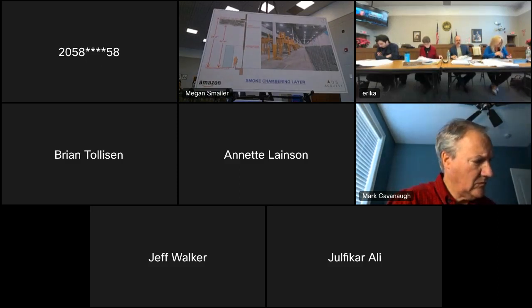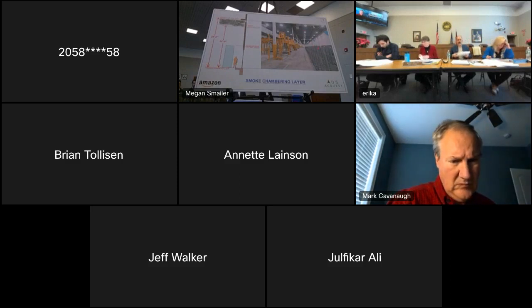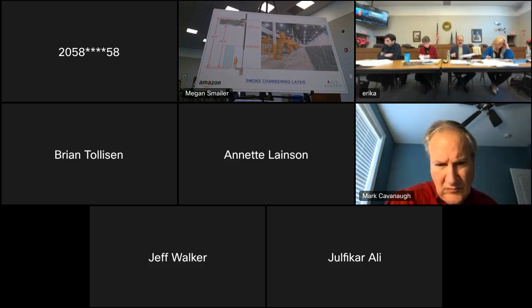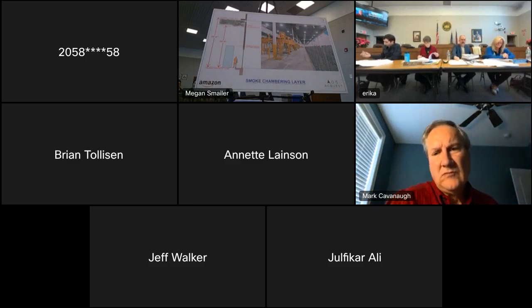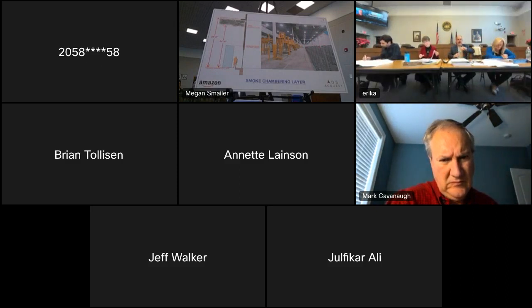Here again, you take a look at the height of the racks in proximity to that tall height of the ceiling. This line represents the smoke interface layer. When we run a smoke model, we pick a location on the floor where the fire is likely to start, if one starts, that would generate enough smoke and hot gases to set off the sprinkler system. I'll show you in another slide where that takes place in this particular facility.